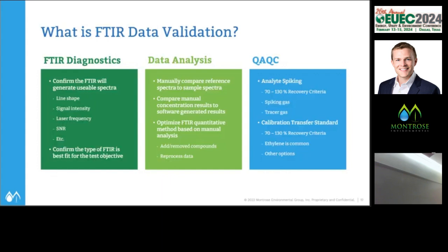So for validation, I won't go too deep into this. There's basically 3 buckets of why we do this, and this is in US EPA methodology. This is a requirement, but so few firms actually do this because of lack of understanding, new regulatory people. They just don't know what validation is. They're told that, hey, it's good, and they take the word for it. So what validation is doing is on the instrument side, it's making sure that we have the proper FTIR configuration for the job, right? That we've got good line shapes, everything's looking good on signal to noise ratio. It's the right tool for the job.